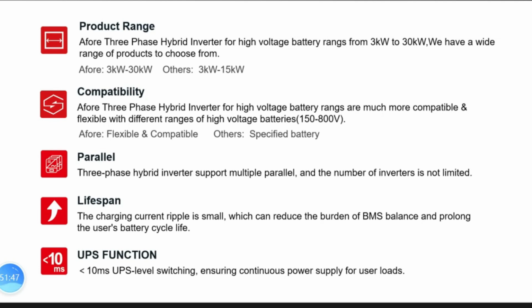Yeah. Well, especially for the batteries, I guess. If the capacity is higher, you have a lower C rating, so the battery has a longer lifespan. Yes, yeah. So that is a good point. If you oversize the batteries more, you discharge them at a lower rate to restrict the C rating. I'd probably only recommend about 0.5 C anyway on the batteries to give them the lifespan that we would expect to have. Yeah, but that makes sense if you over-capacitate your battery system for a longer lifespan. But plus the other thing with that is things like using time of use tariffs, where you're charging it from AC over the winter. You need a bigger capacity battery if you're calculating what the daily use is.